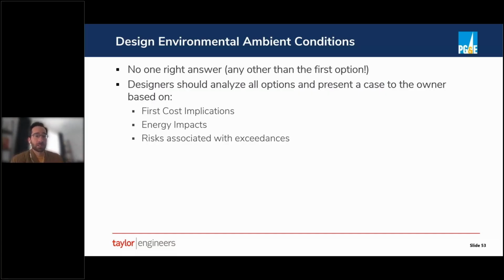Sometimes oversizing is a good thing. As an example, if you oversize cooling towers for that once in a 50-year event, well, it's going to be the case that the cooling tower fans are going to have to work less hard during most conditions in order to meet the target conditions. So there can be a first cost hit, perhaps a long-term energy efficiency benefit of some oversize.